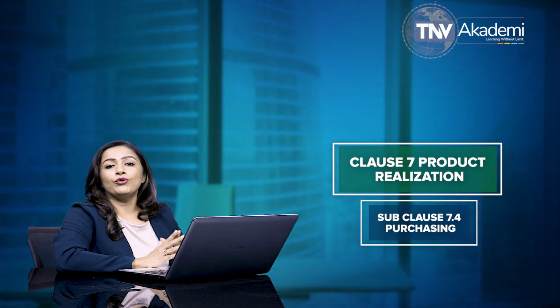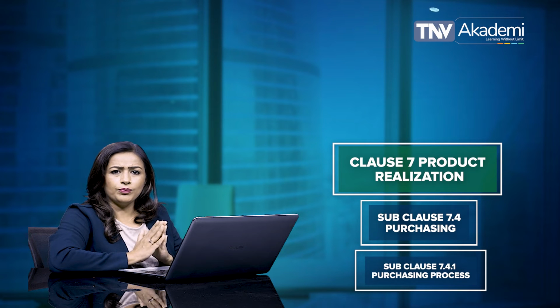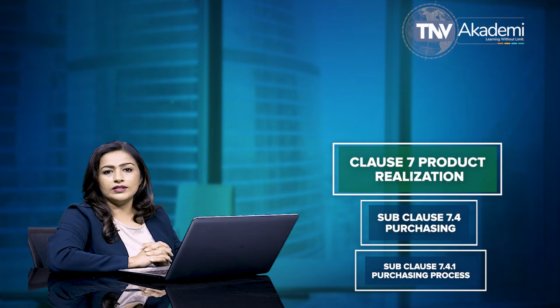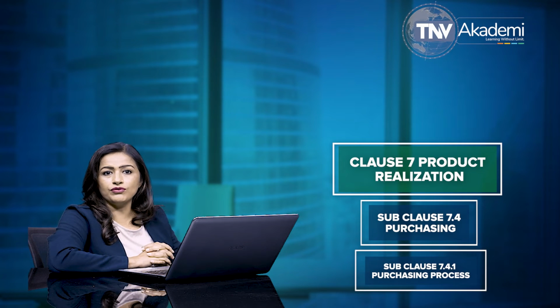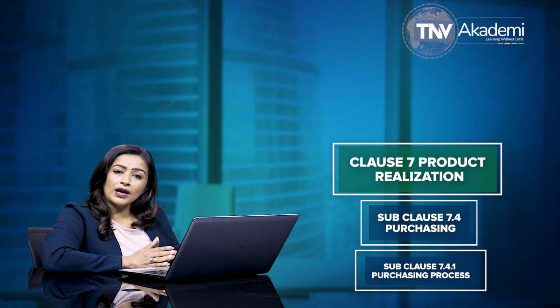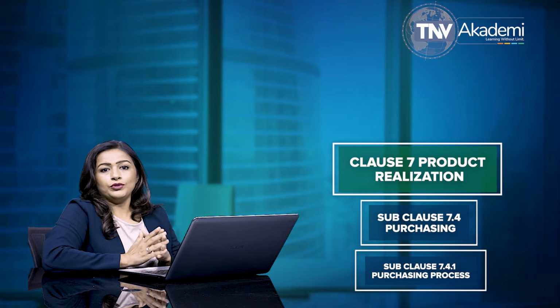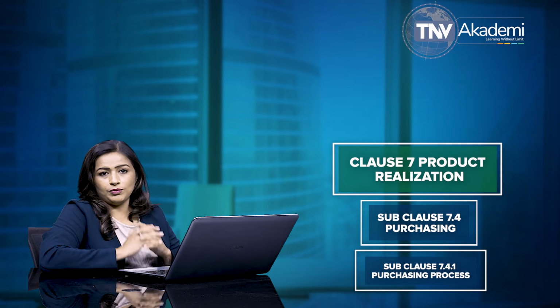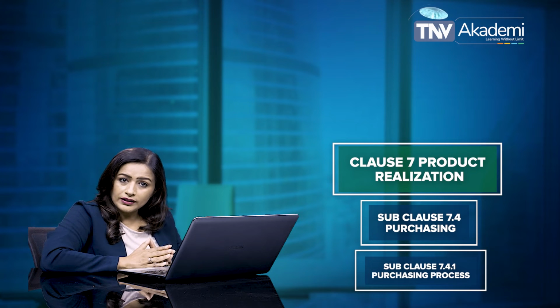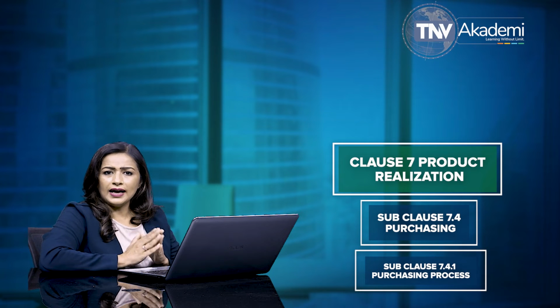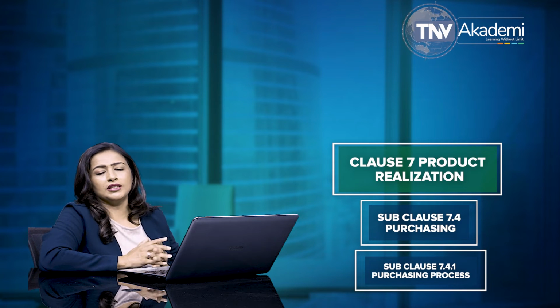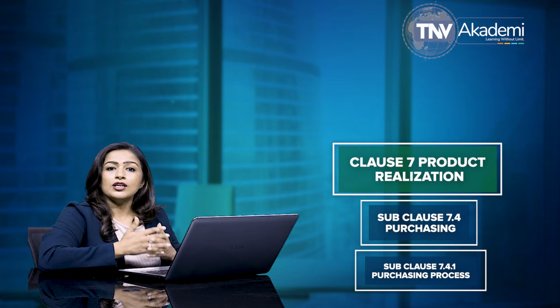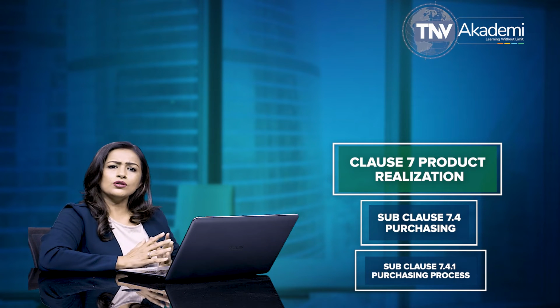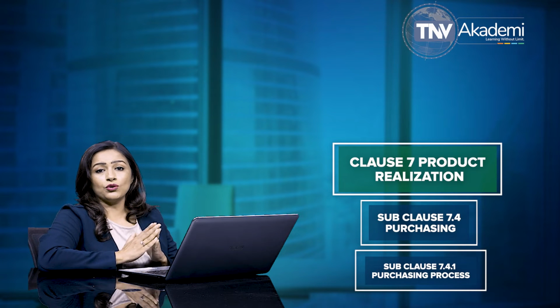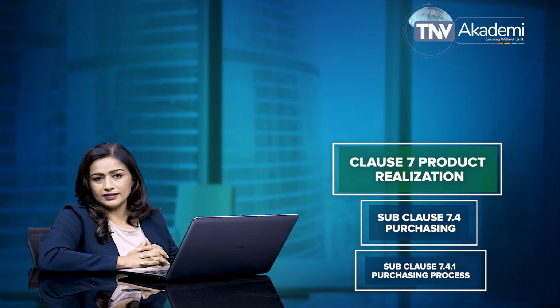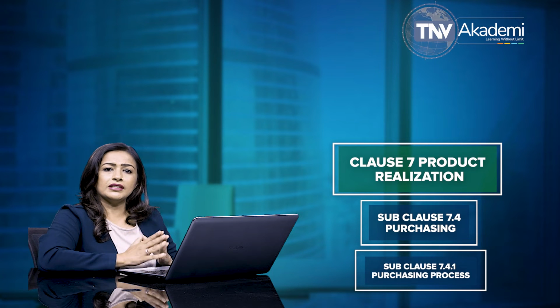Let's discuss subclause 7.4, Purchasing. Let me talk about subclause 7.4.1, Purchasing Process. This subclause 7.4.1 of ISO 13485 states that the organization is required to document procedures to ensure that purchased product conforms to specified purchasing information. As per this clause, the organization is required to establish criteria for the evaluation and selection of suppliers. The criteria must be based on the supplier's ability to provide product that meets the organization's requirements, based on the performance of the supplier, and based on the effect of the purchased product on the quality of the medical device, proportionate to the risk associated with the medical device.